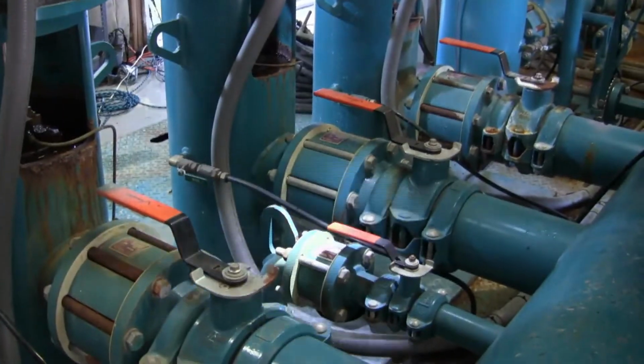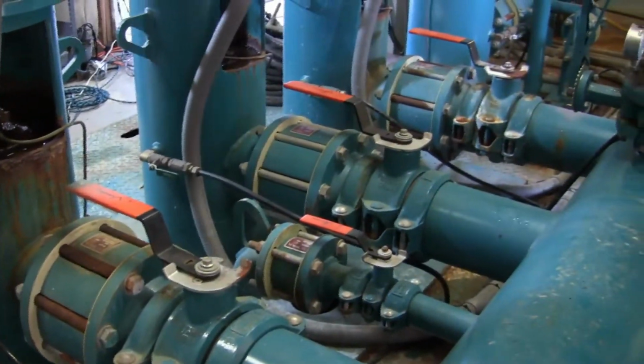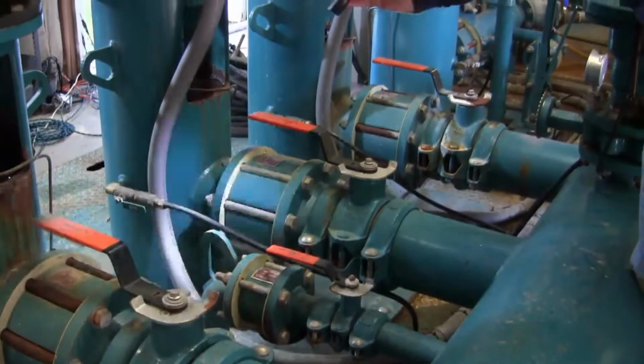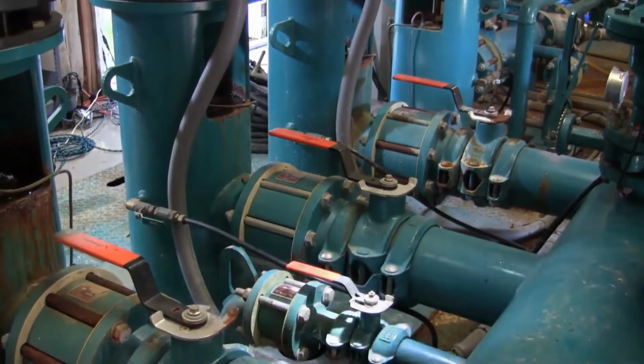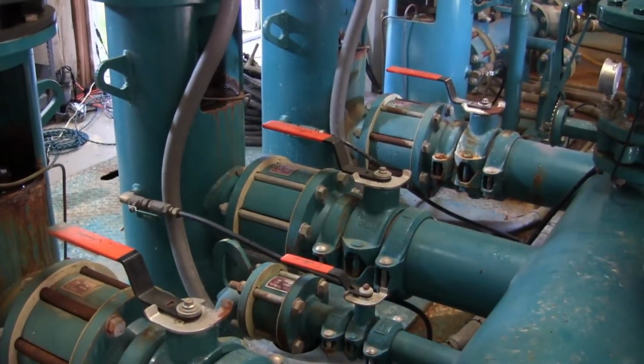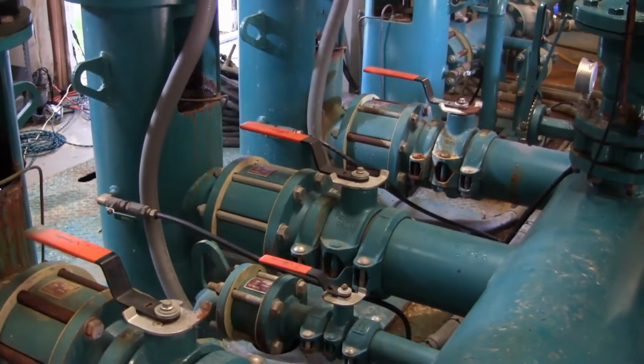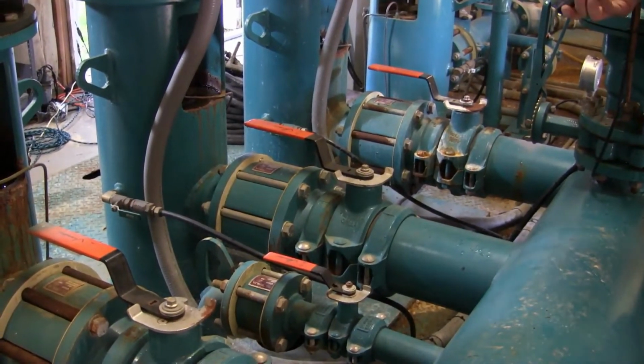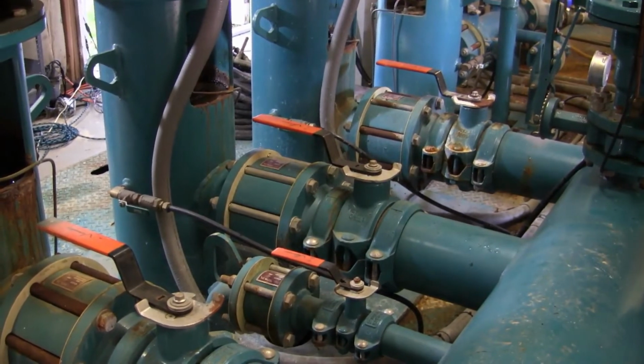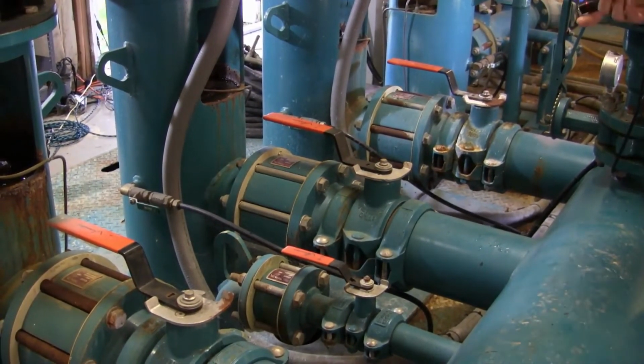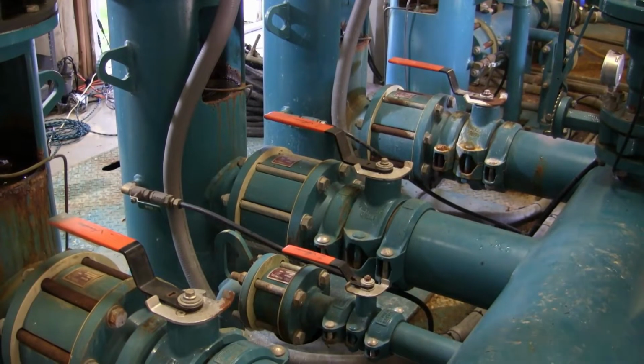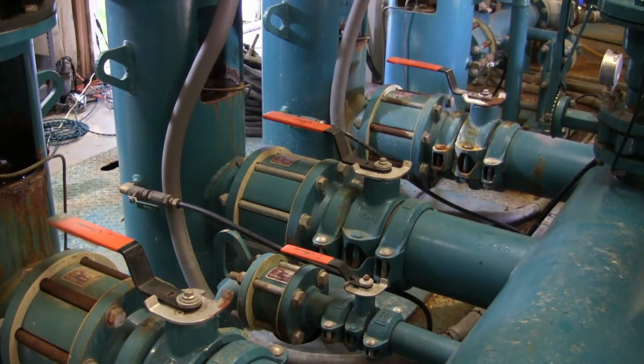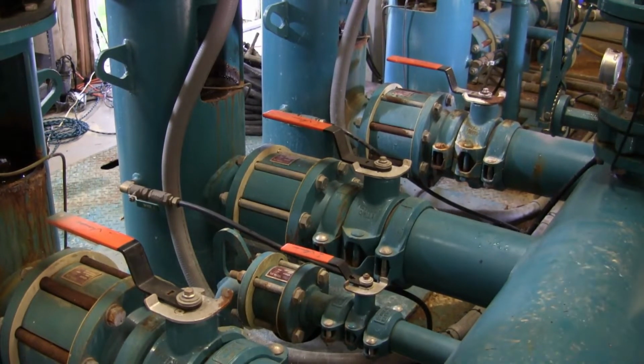I will check, first of all, there's check valves on each pump. When the system is not running but pressurized, you can listen to hear if there's water going back through there. That could be, if your PM pump is cycling a lot, one of the causes. In addition to maybe a head leaking on the course, you might have a check valve leaking. That's something that's really easily repaired. Or not repaired, but replaced. You just loosen that up, drop a new check valve in, and you're good to go.